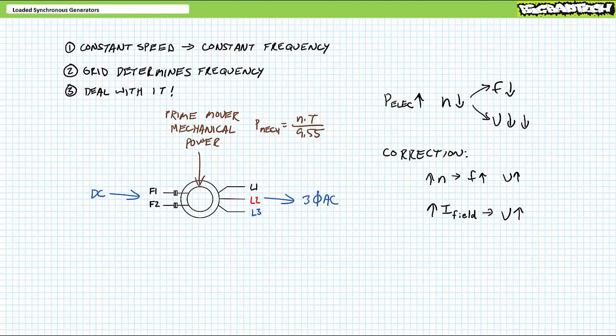Now keep in mind, again, this is not a static load scenario, but can change over time. Consider an occasion where in this compensated state, the electrical load suddenly demands more real electrical power. Again, the prime mover slows down because of increased oppositional torque, and again, the frequency would drop, and voltage magnitude would again decrease due to the combined effects of reduced induction and increased losses internal to windings. Again, the operator would have to further increase mechanical power delivered to the prime mover so it speeds up and frequency stabilizes, then fine-tune field current so voltage magnitude stabilizes.